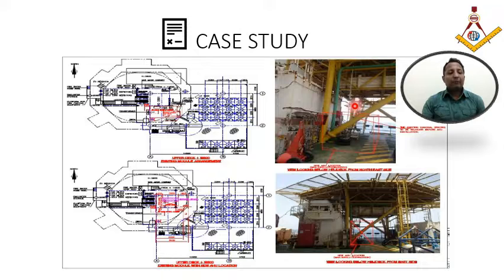There is a case study over here which I would wish to cover. This is a standalone platform. This is not a LQ platform, and if you see, this is a room over here, and this is the length of the room. I think it's close to around 8 meters by 3 to 4 meters. This is the electrical room, and normally you would wonder that this is a very small room, and even a window AC can do the job. But a window AC is strictly forbidden in offshore applications because it doesn't create any pressurization. It works on simply the recirculation principle. So you must be wondering what kind of HVAC system is proposed over here.